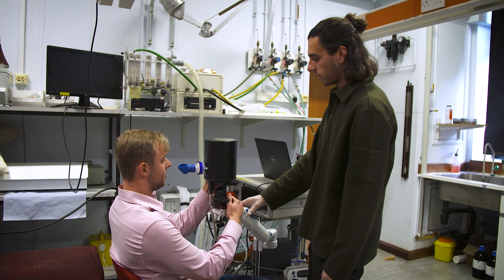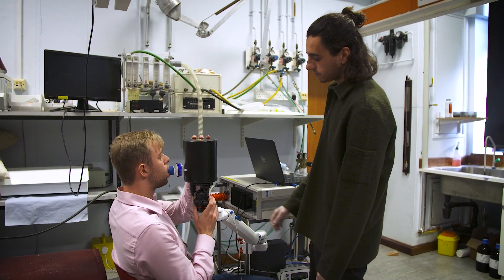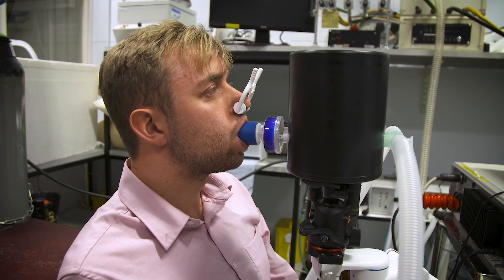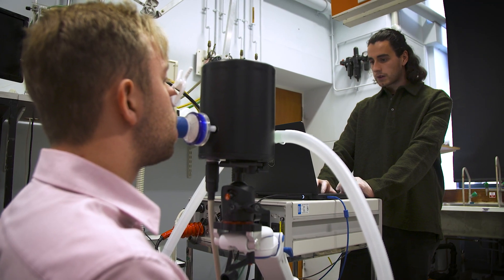The molecular flow sensor measures very precisely the gas concentrations in people's breath using laser absorption spectroscopy. When combined with flow measurements, that allows us to make very precise measures of gas exchange. This works on the principle that the different gases in the breath absorb laser light or radiation at different frequencies, so you can use lasers to selectively probe the concentrations of each of the gases that you breathe.